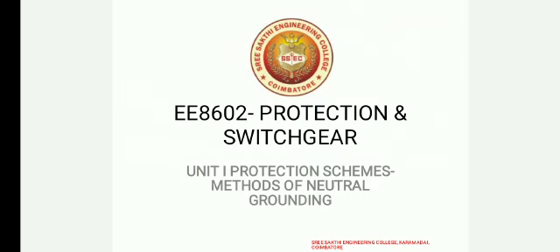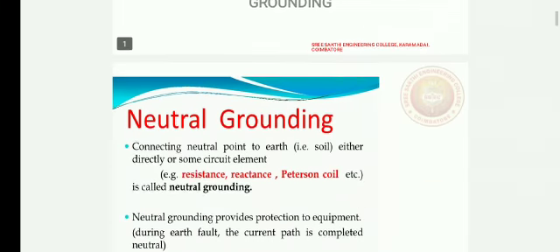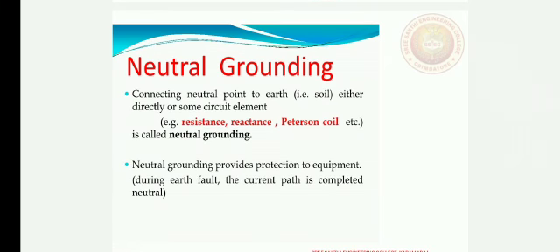Today we are going to discuss methods of neutral grounding. Now, what is neutral grounding? The earthing or grounding is nothing but the connection of the neutral point of the supply system to the general mass of earth in such a way that immediate discharge of electricity can take place without danger. Otherwise, connecting the neutral point to earth either directly or by using some other elements such as resistance, reactance, coil, etc. is called neutral grounding.